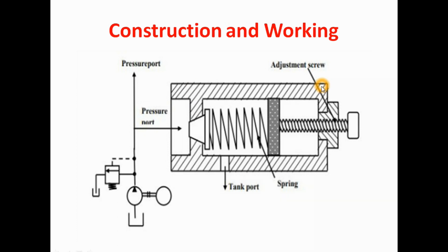You can see here — this is the body of the PRV, this is the adjusting screw, this is the spring, and this is the port. Whenever excess pressure is generated in the hydraulic circuit, due to the excess pressure this port gets open, this spring gets compressed, and oil starts to drain from this port and goes back to the hydraulic power pack. By adjusting this screw, we can change the setting pressure — that means at which pressure this PRV should open and drain the oil.